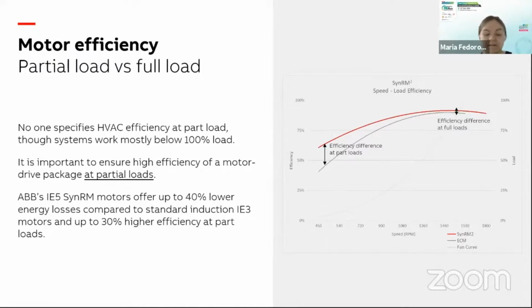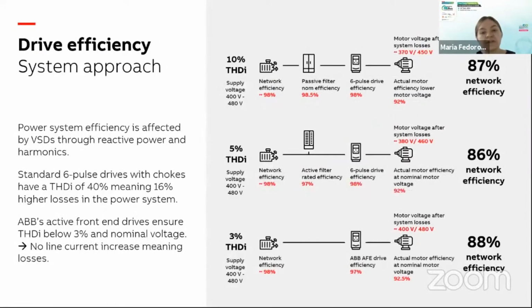From ABB's side, we've recently introduced an IE5 synchronous reluctance motor technology, which offers up to 40% lower energy losses compared to standard induction IE3 motors. Their part load efficiency can differ from standard motor technologies by as much as 30%. So again, look at part load efficiencies when selecting your motor technologies. I'm not going to go into too much detail about drives, but my main message is to look at what kind of effect variable speed drives bring to your system.